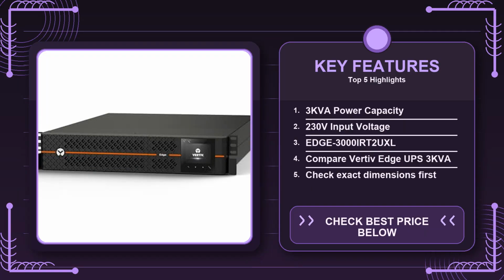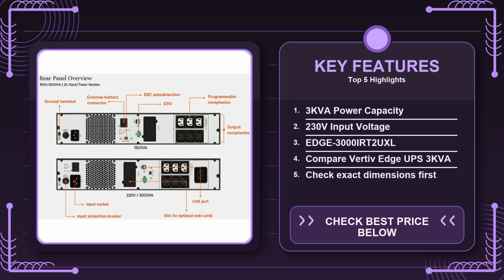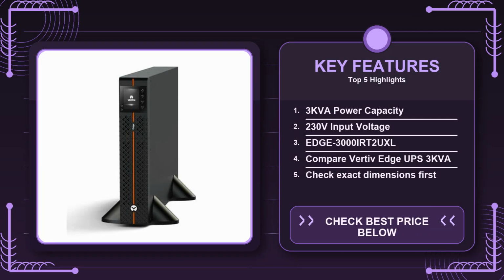Vertiv designed this UPS so you can replace the battery modules without powering down the unit, a feature you normally see in enterprise-grade equipment. In a small office, that means you can schedule a battery change during a regular maintenance window and avoid an unexpected outage.